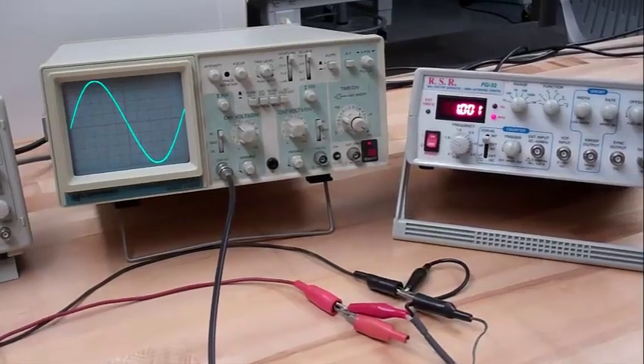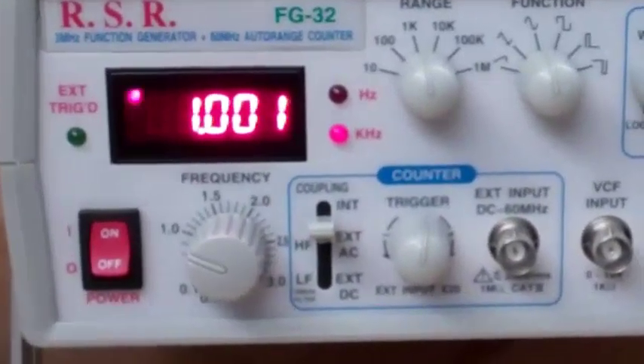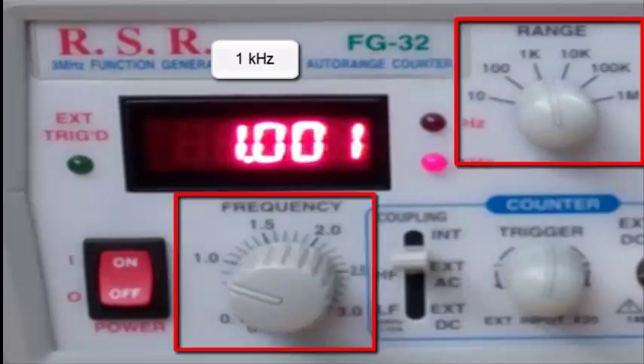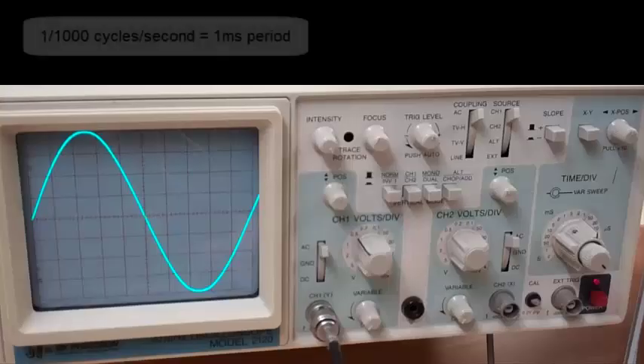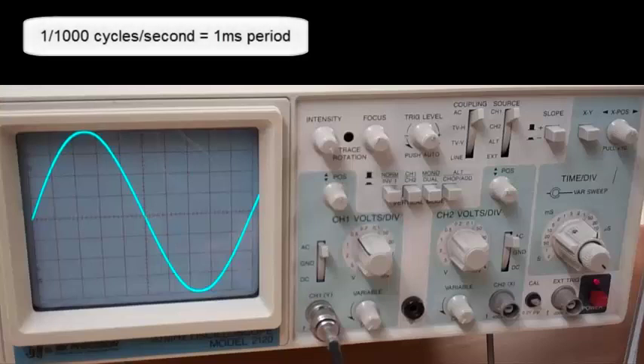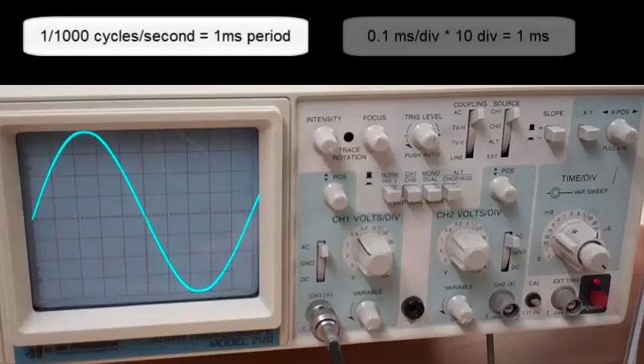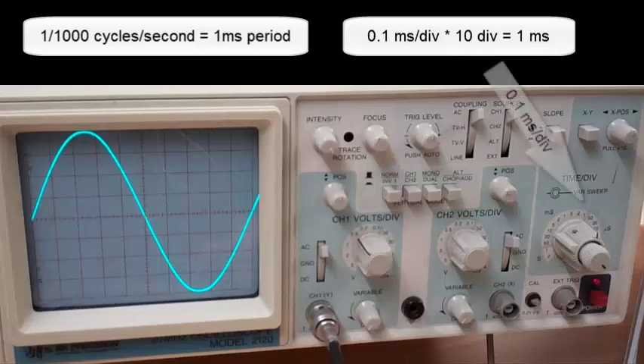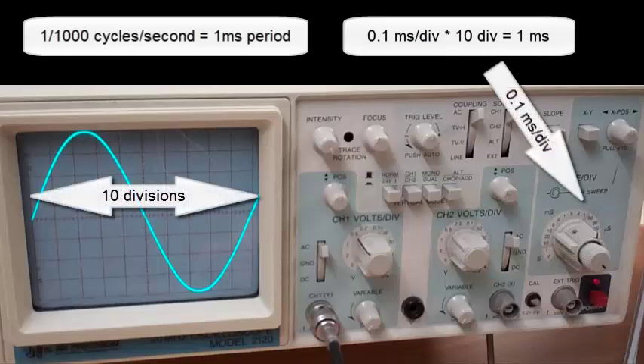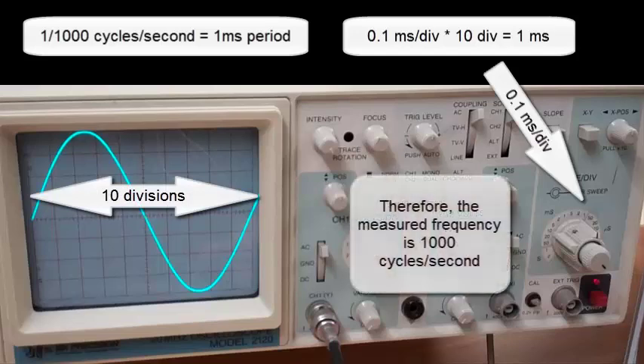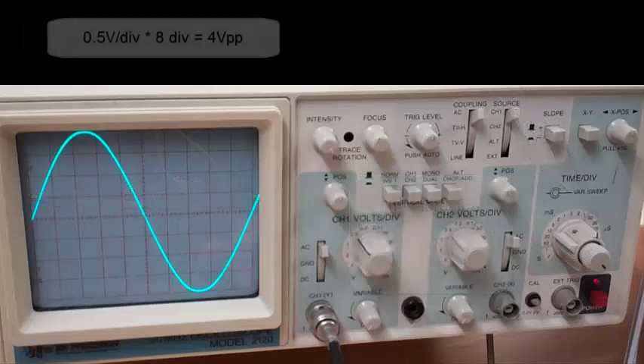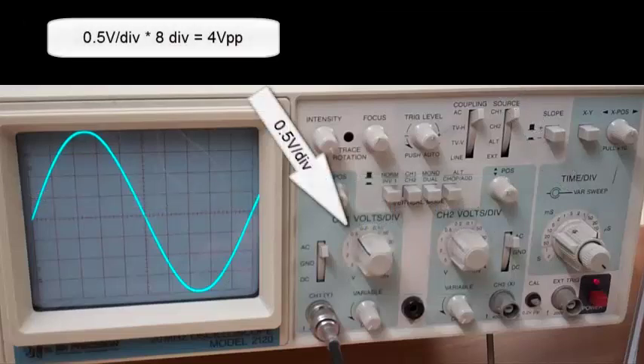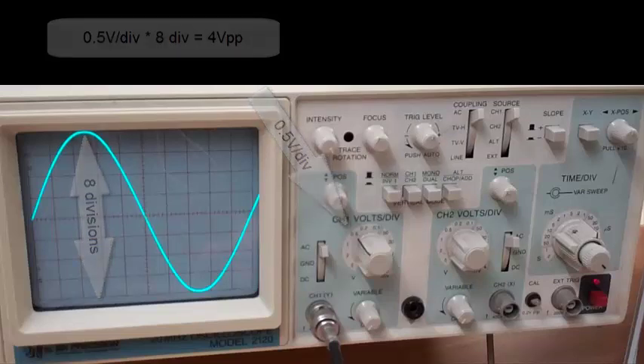Evaluate the peak-to-peak voltage and the frequency. Set the function generator to 1000 Hz. The inverse of 1000 cycles per second is a 1 millisecond period. 0.1 milliseconds per division times 10 divisions equals 1 millisecond, so the measured frequency is 1000 cycles per second. 0.5 volts per division multiplied by 8 divisions equals 4 volts peak to peak.